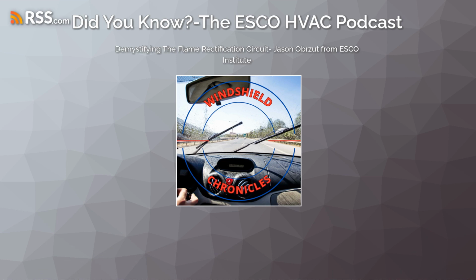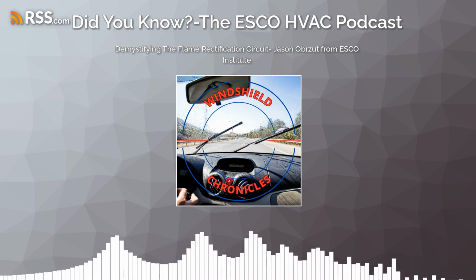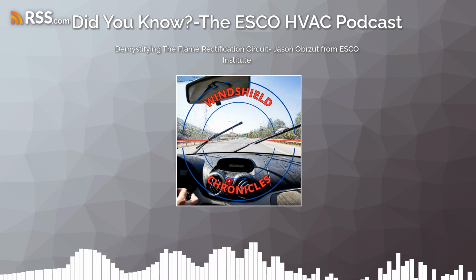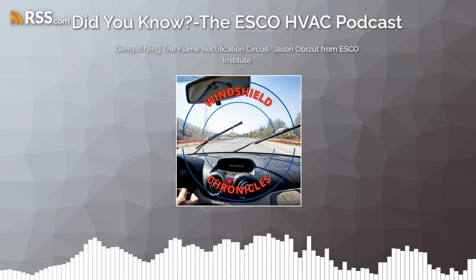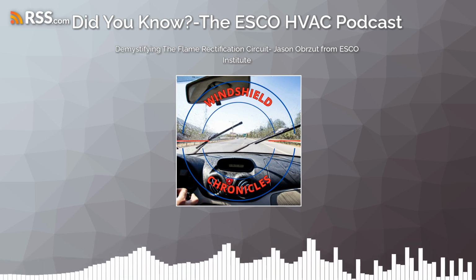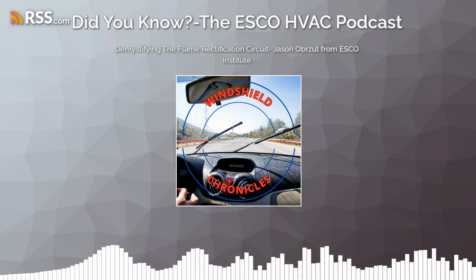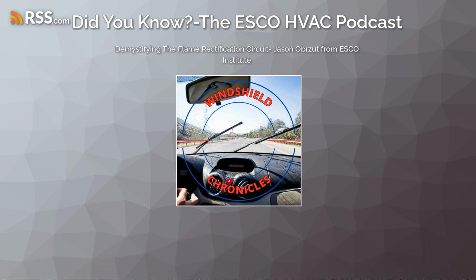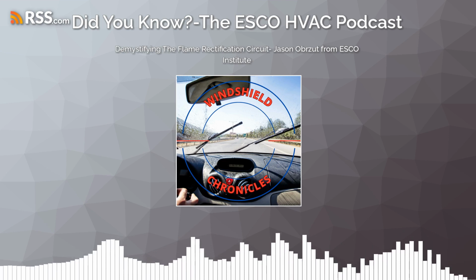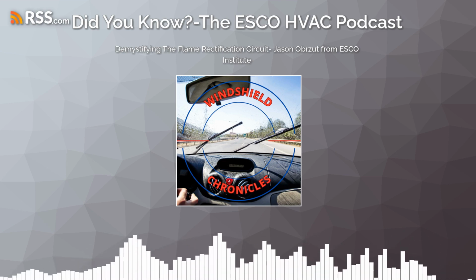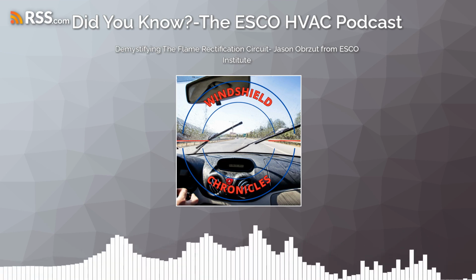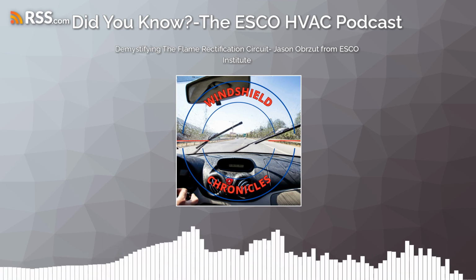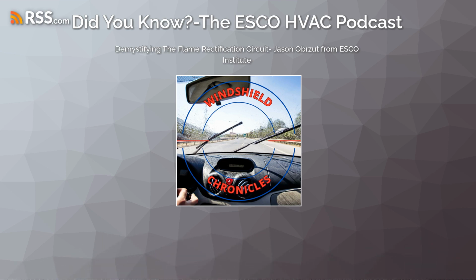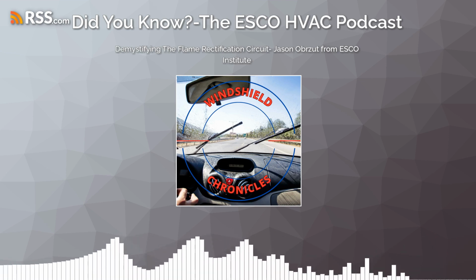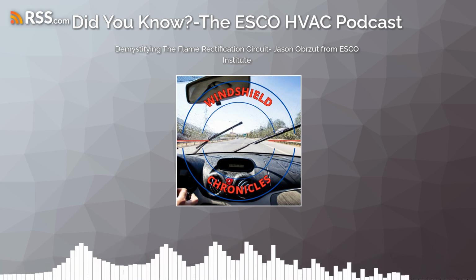Literally just disconnecting the wire and putting our meter in. So all we've done is complete that loop. If we go back to that wiring diagram, we'll see exactly what I just did. I took the orange wire off from the flame rod and put my meter in series so that my meter is measuring the current that is passing through. If we're reading amps of any kind, we're reading the current. And that's actually what we're going to do.